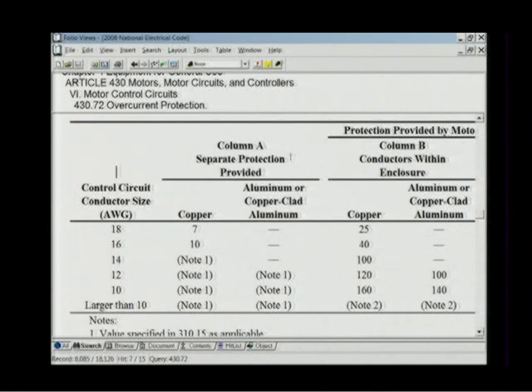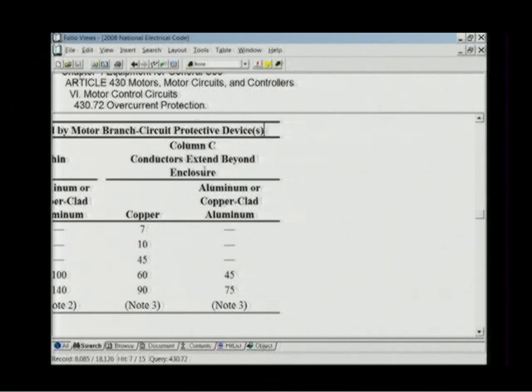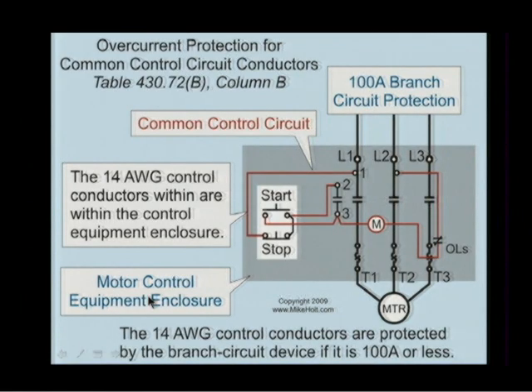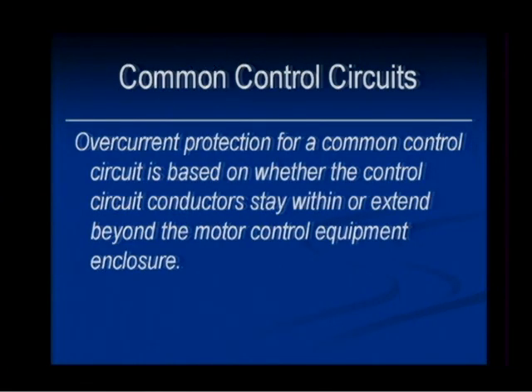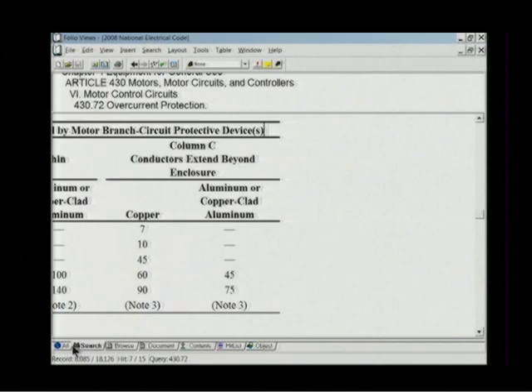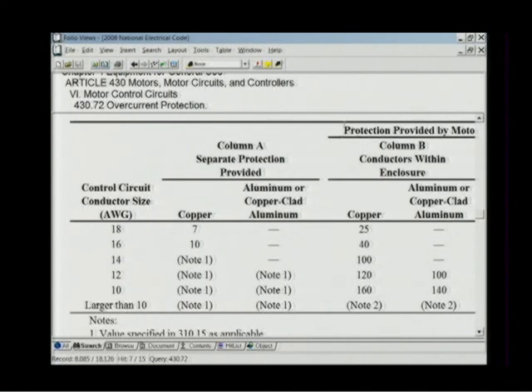And we've got 18, 16, and 14, so let's go to conductors that extend beyond: 18, 16, 14, etc. Let's see if we have a slide next. So that one is column B, done by the manufacturer. Overcurrent protection for a common control circuit is based on whether the control circuit stays within or extends beyond the motor control equipment enclosure. Let's take a look at that code. Remember, extending is going to be column C, and within is column B. If it's within, we don't worry about it. If it extends, we do.